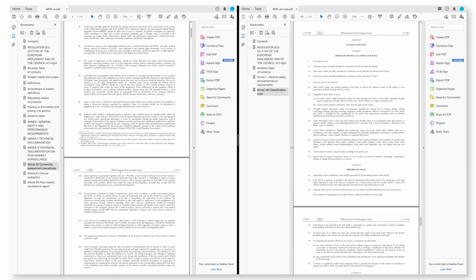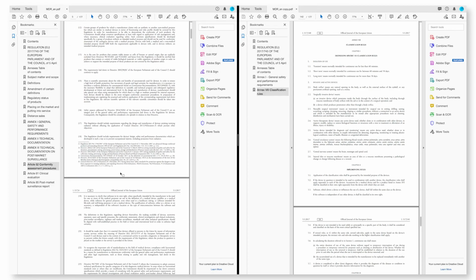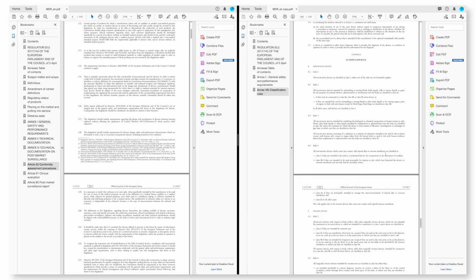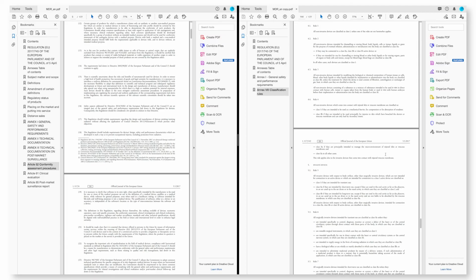When you have the bookmarks set up, I recommend you to have two PDFs open at the same time when you're reading the MDR, at least in the beginning, to be able to scroll between the references without losing track of where you were. And my other tip: carefully read the annex related to the notified bodies and their process requirements. That is Annex 7, Section 4. This is very good for your understanding of what the notified body will ask you as a manufacturer and actually explains the way of getting your sought-after MDR certificates.